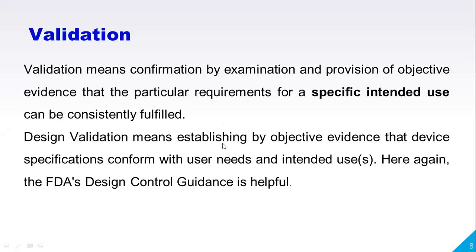Design validation means establishing by objective evidence that the device specifications conform with the user needs and intended use. See, this is the concept. The objective evidence that the device specifications conform with the user needs and intended use. As per intended use and also the user needs, a particular medical device is manufactured, and we confirm that. This is the validation. Right? Here again, the FDA design control guidance is also helpful. Just as the FDA gave guidelines for verification, it also gives some specific guidelines for validation. So you can follow those guidelines for validation of medical devices. That is the validation concept.